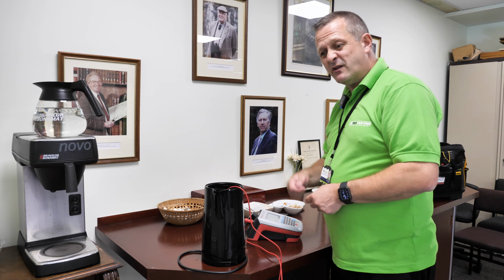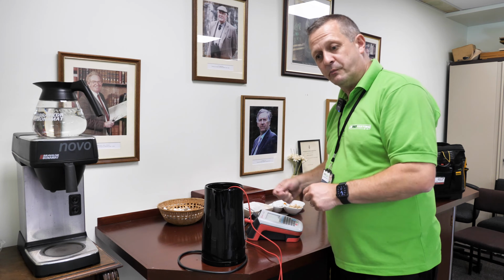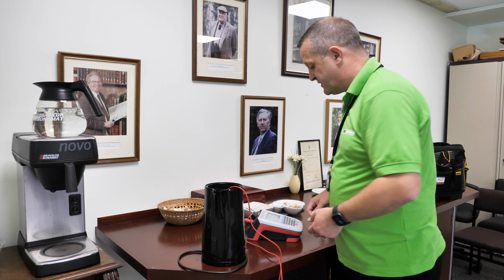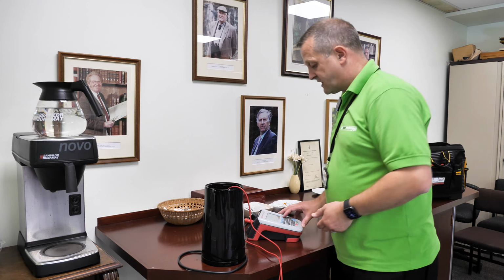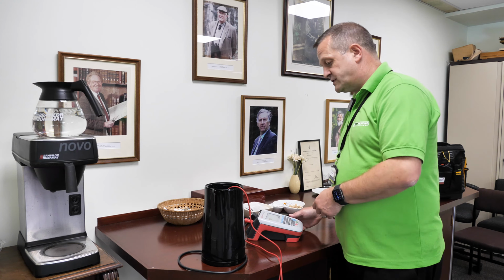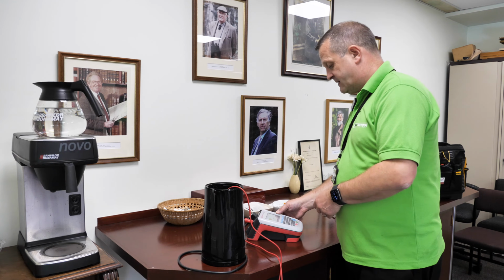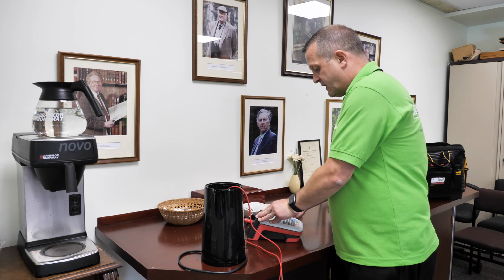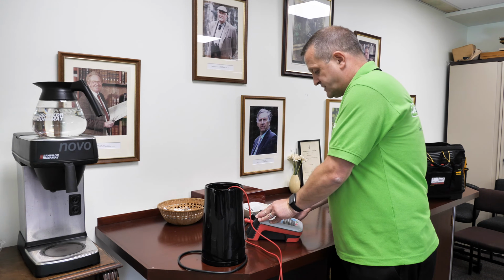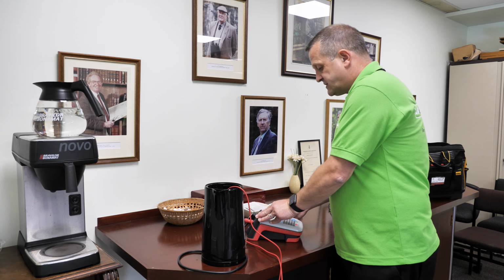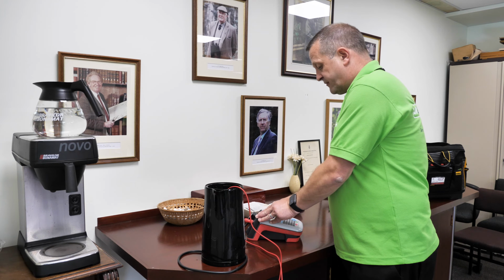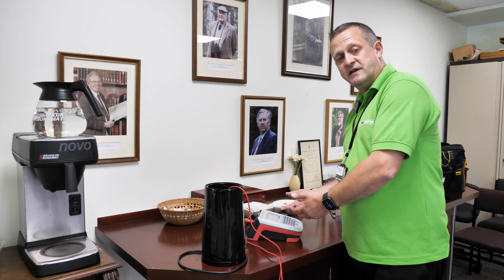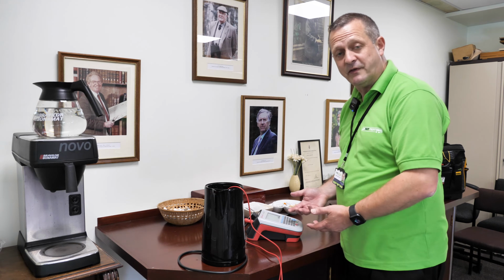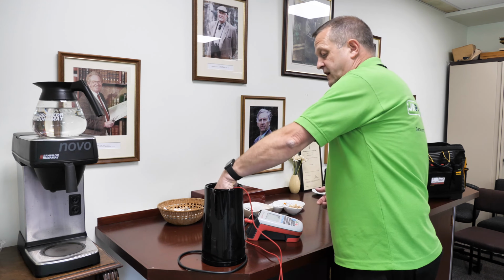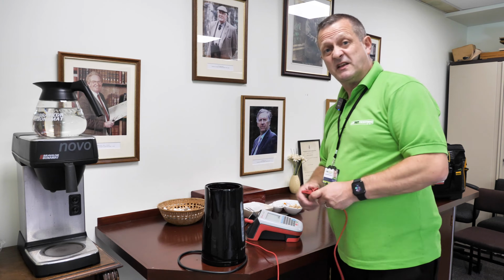If it has got quite a bit of lime scale, just get a screwdriver or the end of your crocodile clip or your prong just to scrape that down to expose the metal better to get a result. But again, all it is a class 1 appliance test, so we're just going to go through to test the earth. And that's fine, and then all it'll do then is continue with the insulation test. And again, that's coming up fine. So yeah, again, we'll record the details onto the machine or onto your laptop or paper, whichever method you prefer to use. We'll attach a label onto it to say that it's passed, and that's it, complete.